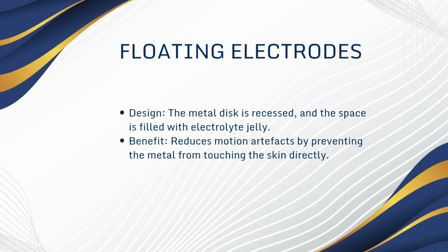Here, the metal doesn't actually touch the skin. It sits in a recessed pocket filled with jelly. This cushion of jelly helps keep the signal stable even if the patient is moving around.